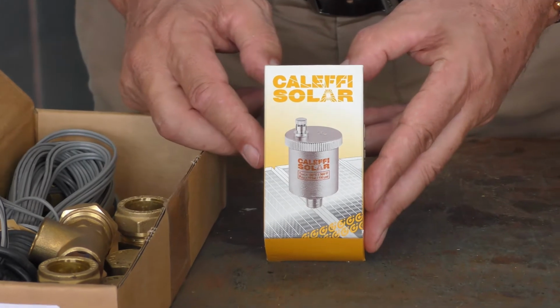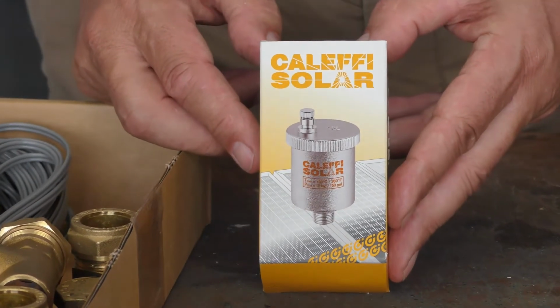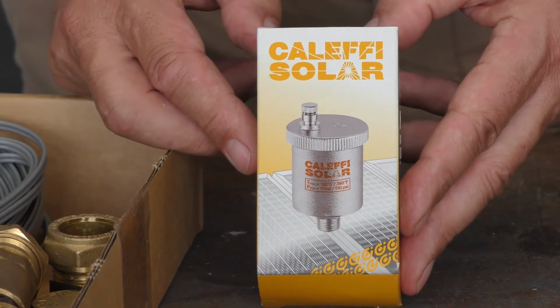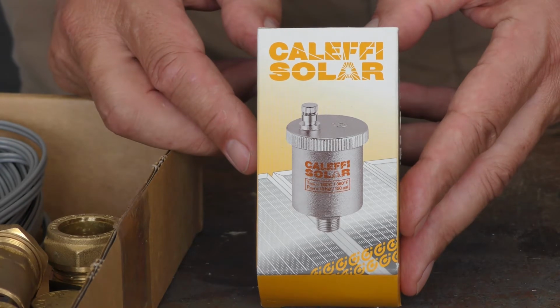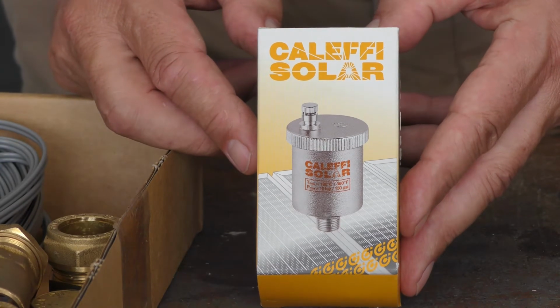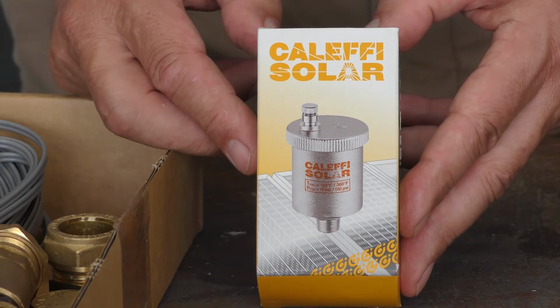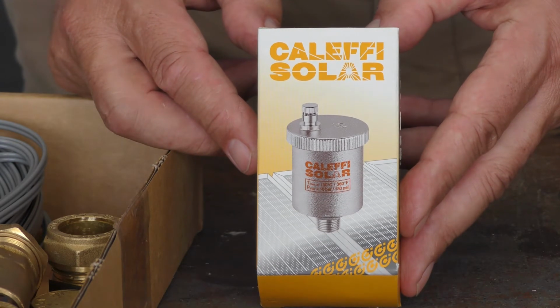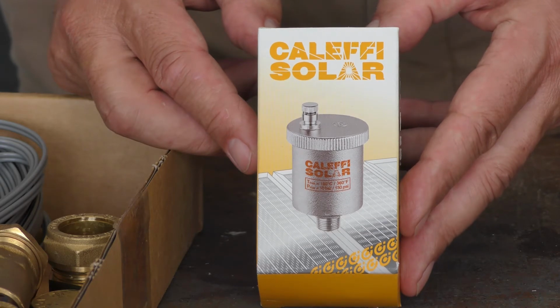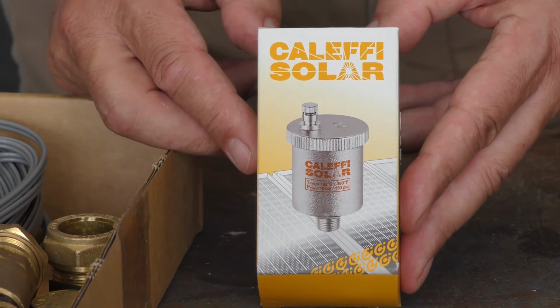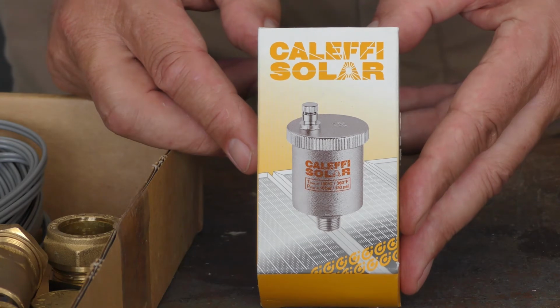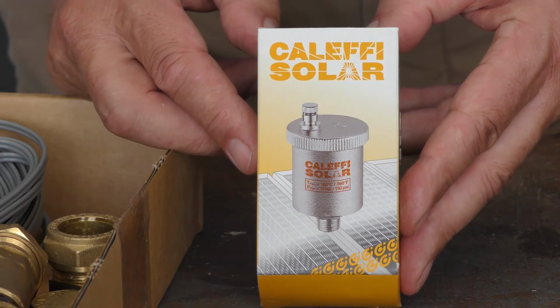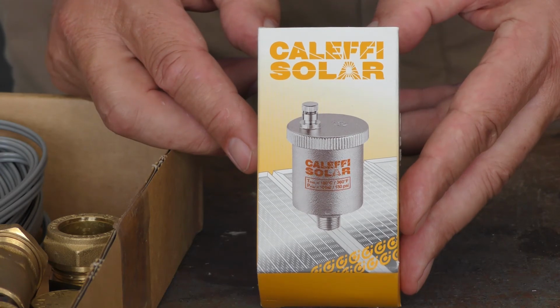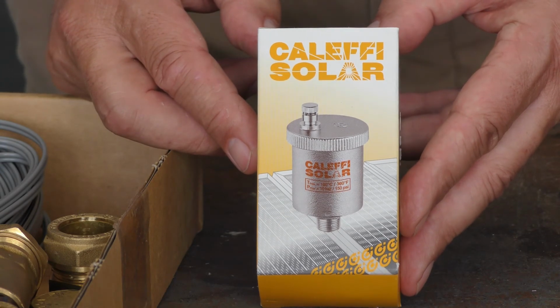This is a high temperature valve. You can get these air vent valves in standard hot water design, which would be no more than 70, 80 degrees. But this one, because of our high stagnation temperatures of over 140 degrees in our collectors, you need to ensure that it is a high temperature solar air vent valve. The diaphragm inside it is able to manage the temperatures that it can obtain up in the collector. So please ensure that you don't put anything else there except the one that we provide and recommend in our system.